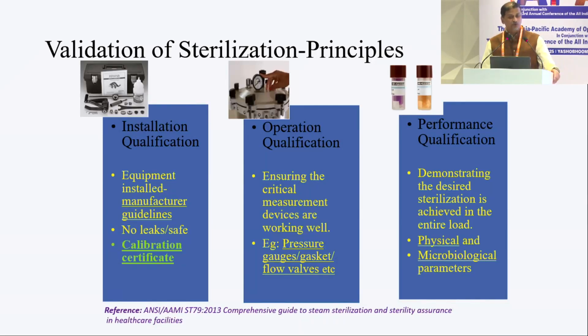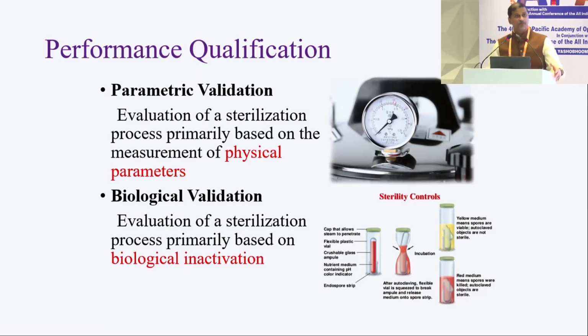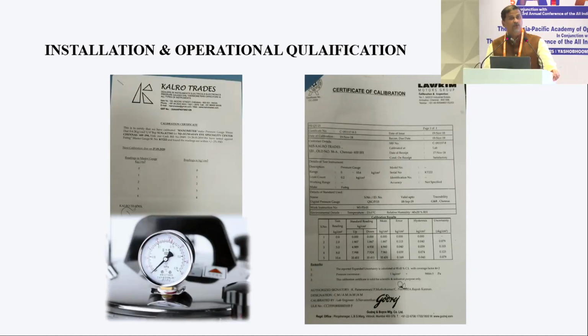What does installation qualification mean? Once the manufacturer sets up the autoclave in your place, he has to give you a calibration certificate showing that the machine is working well. The operation qualification is for you to check physically and manually all the pressure gauges and the valves, and the performance qualification is all the validation indicators, which I'll be talking about subsequently. Performance qualification is of two types: physical monitoring and the biological indicator. So this is a certificate which will be provided by the manufacturer to you when you buy the autoclave. Please ensure that the date and signature, everything, are accurate before you take the autoclave into your unit.